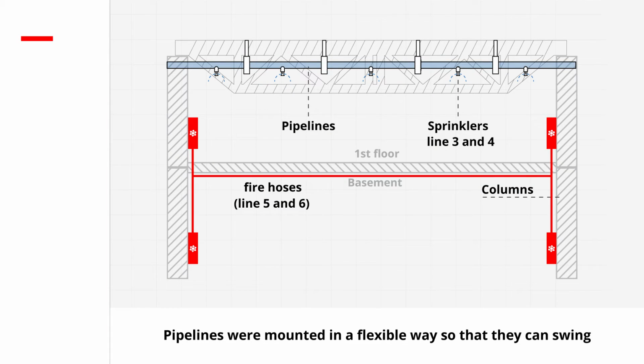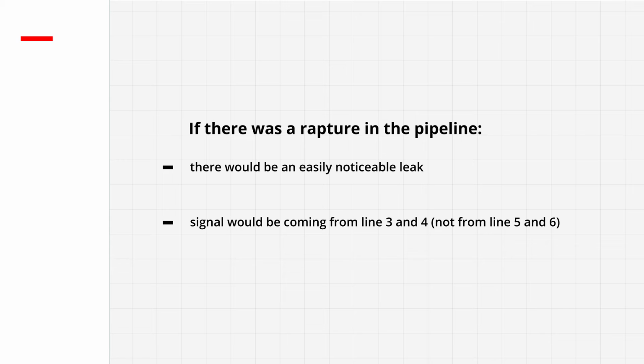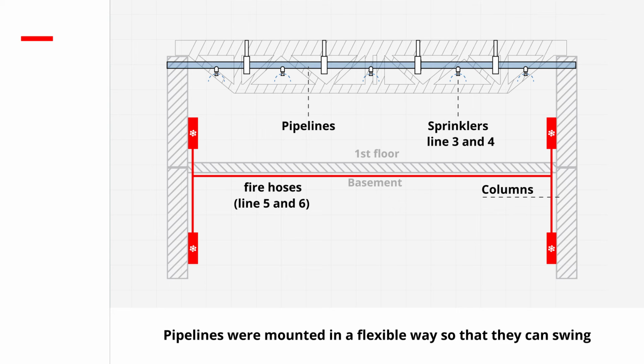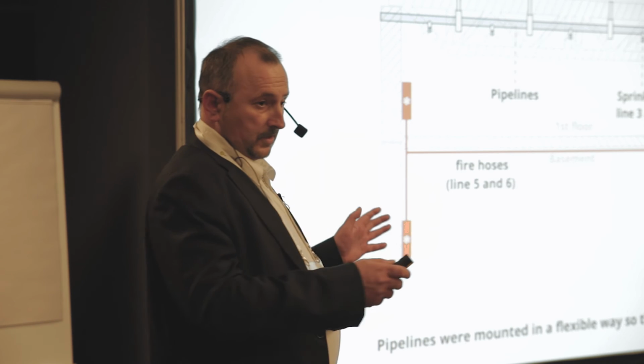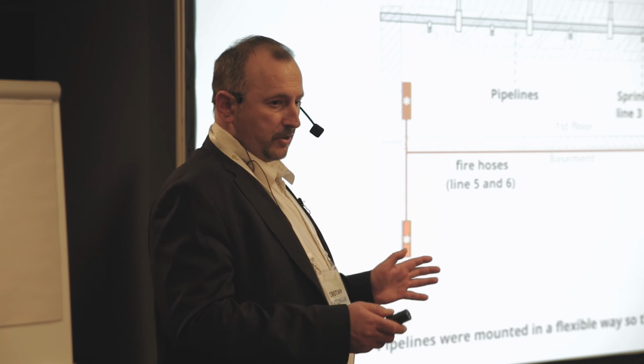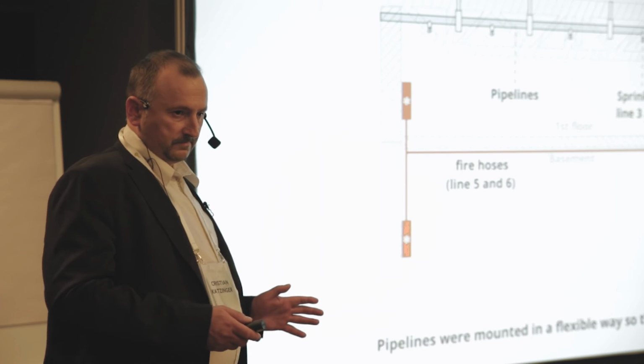The other part is the sprinkler system. I explained that there are pipes mounted under the roof, but these aren't the pipes for the fire hose lines 5 and 6 where the alarm came from; they are the pipes from lines 3 and 4. And even if there were a leakage inside a wet system, you can be sure you would see the problem immediately, because a sprinkler which breaks opens a valve, and such a sprinkler at 1 bar pressure releases about 80 liters per minute of water downwards.